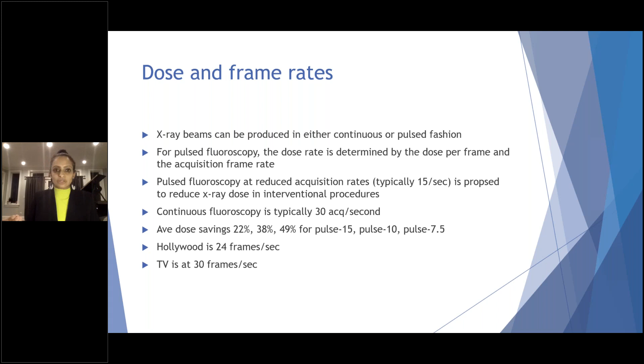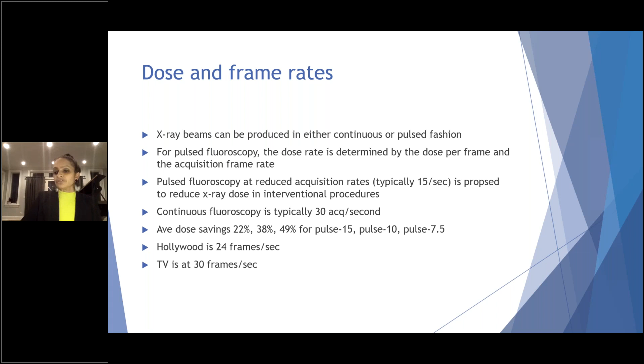And there was a dose savings of 22% versus 38% versus 49%. So when you're using a pulse mode as compared to a continuous mode for a procedure, you could be saving about 50% dose of your X-rays to your patient, to yourself, and as well to your personnel. I hope that made sense. It's always strange doing these talks because I don't see anyone's faces. I can't tell if what I'm saying is making sense.